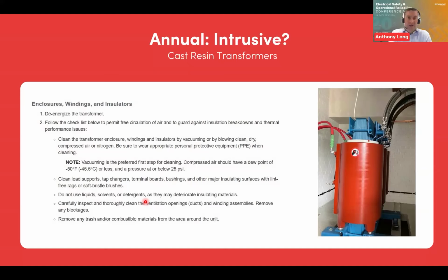So we looked at a lot of NFPA 70B, if it's in condition 1, it would tell you 60 months. But obviously, if your O&M instructions are saying every 12 months, then you need to be following your O&M instructions. Otherwise, things like warranties and things like that are straight out the window. So you might come into it in 60 months' time to do your inspections, and then all of a sudden you realise, actually, there's a problem with it. But you know what? You're way past your warranty dates for the manufacturer's instructions. So understanding what takes precedence is really, really key.